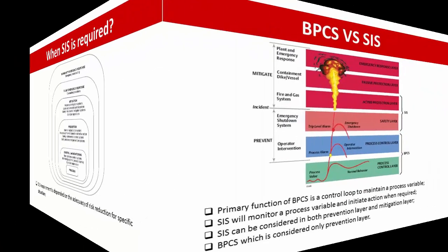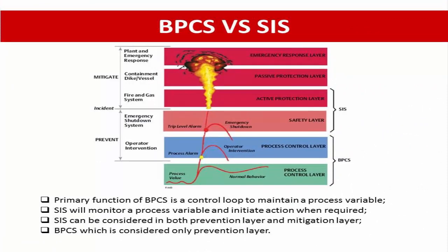Comparing BPCS and SIS: if you think about the components, the SIS and BPCS, or Basic Process Control System, are similar. They are both composed of sensor, controller, and final element. Although the hardware architecture is similar between SIS and BPCS, they are very different in function. The primary function of the BPCS is a control loop, which generally maintains the process variable, whereas the SIS monitors the process variable and initiates action when required.